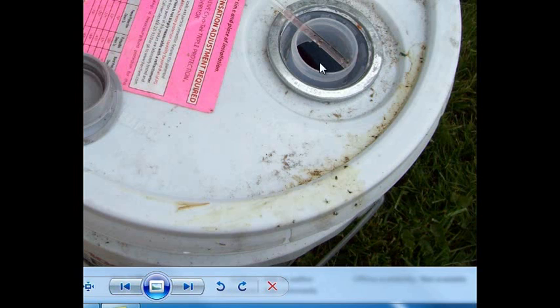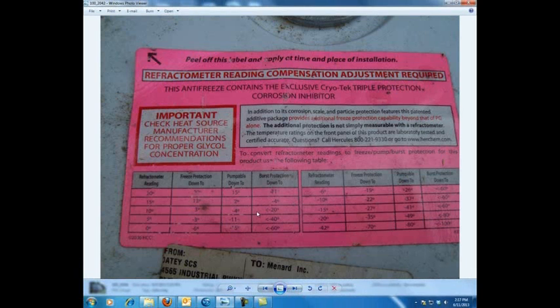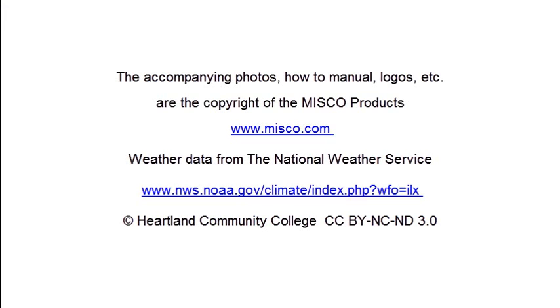Just to recap: you take your reading, take a clean sample of what you've got, put it in your refractometer, and look to see what that percentage is. Then go to the manufacturer's reference chart and read what the correction value is. Every product will be slightly different, and we need to know those values. That, in a nutshell, is how we read the freeze point of a glycol system.